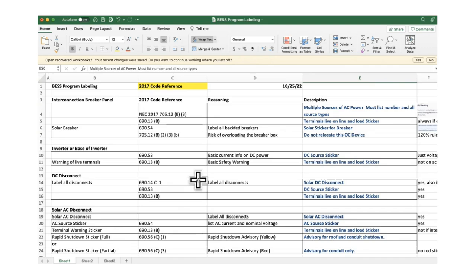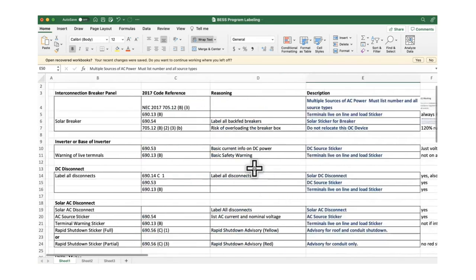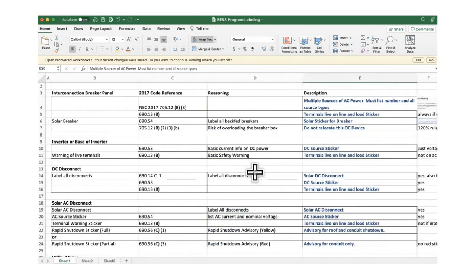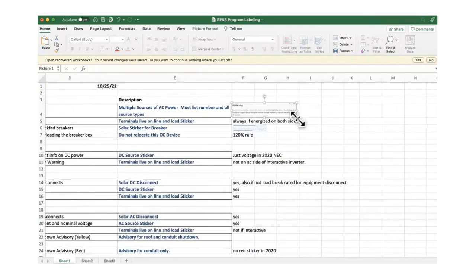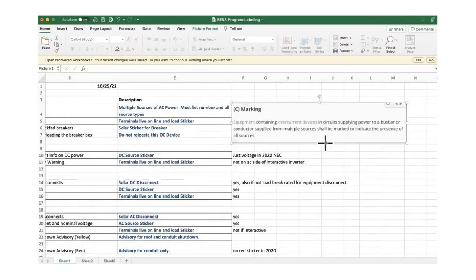So which of these sources has to be shut off from the outside? Yeah, so I mean, we do have to, for PV system, initiate rapid shutdown from outside on 1 and 2 family dwellings. Right. And then also for energy storage systems, we have to be able to shut them down from the outside. And we say energy storage system, that would be the 9540 listed system, which is essentially like the AC side of an energy storage system. Does that make sense there? Yeah, I agree with that.